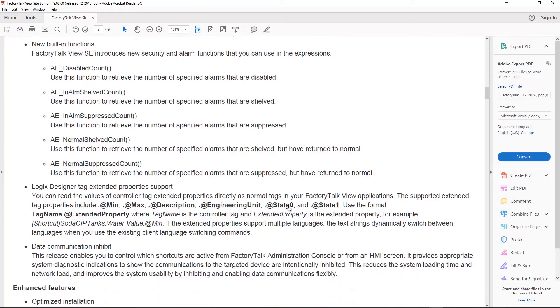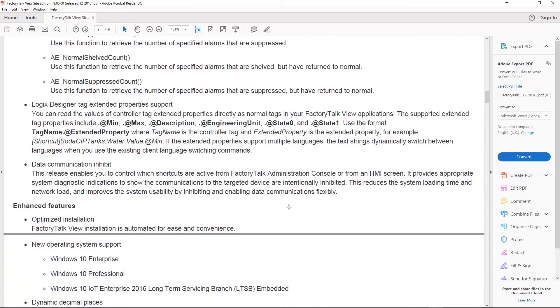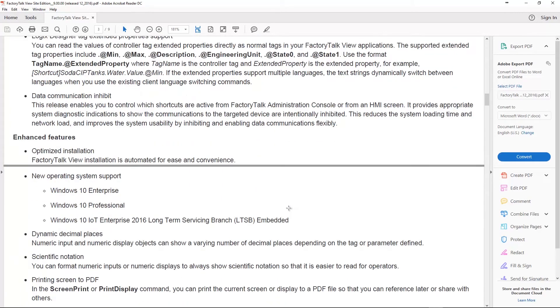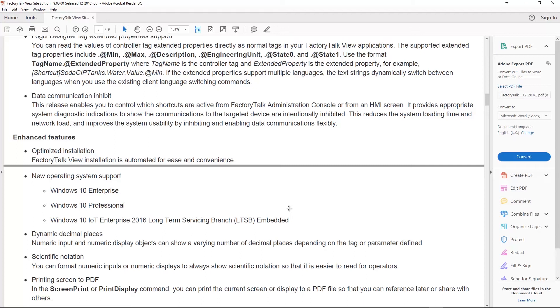Next they added a data communication inhibit bit and this allows you to inhibit like a shortcut. Why would you want to do this? Well let's say you have 20 machines all connected to your FactoryTalk View SE. If one goes down it can really slow down the startup of a client or just the operations of the clients because when it goes to screens that have data from that PLC that's down, not on the network, maybe it's down for servicing, it's trying to connect to all those tags. So by just inhibiting the shortcut we can really speed things up. I haven't tried this feature yet, I'm looking forward to trying it but something people have been asking for for a very long time and I'm very glad they found a way to get it into the package back in version 9.